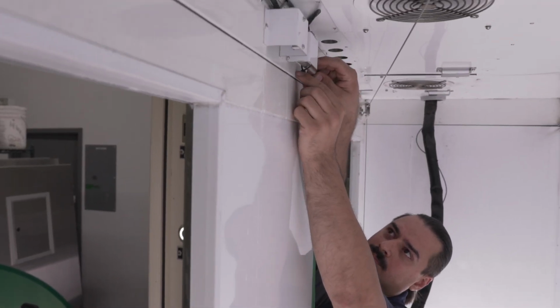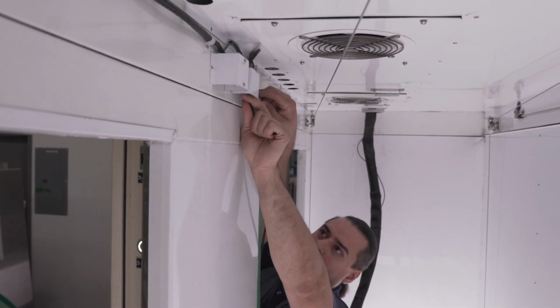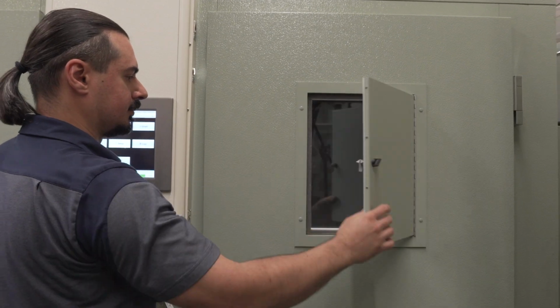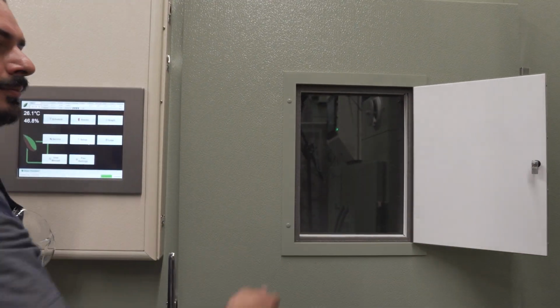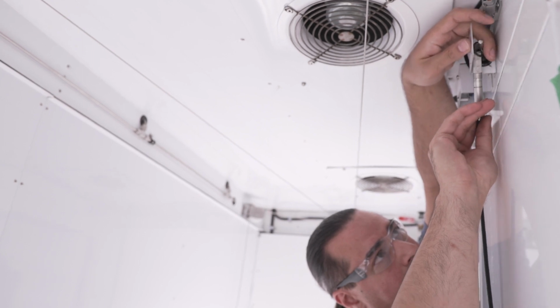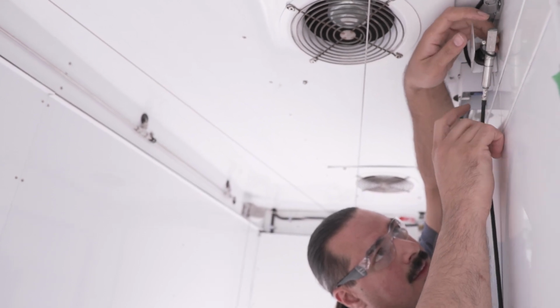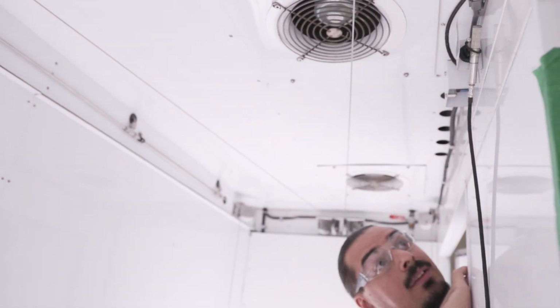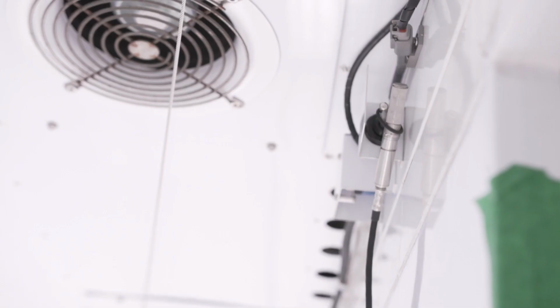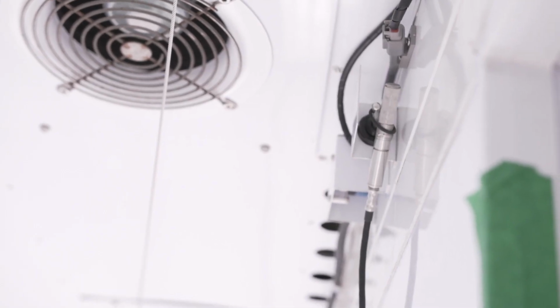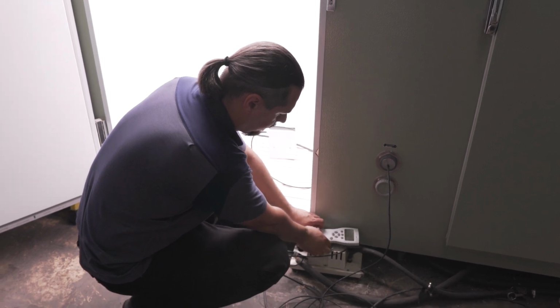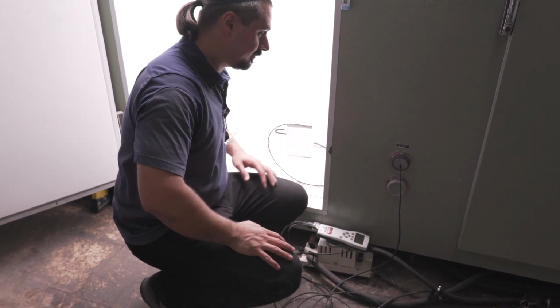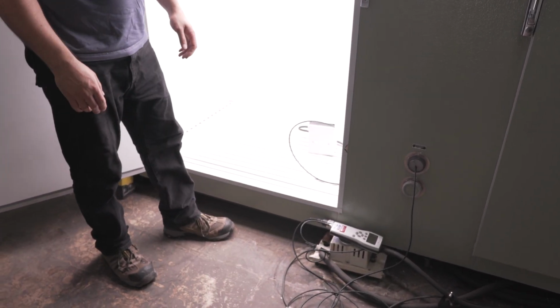Repeat the calibration check for the safety temperature sensor with lights off at max temperature and ensure it is receiving proper airflow. Note that when the lights are on, the safety temperature sensor will read 3 to 10 degrees higher than the chamber temperature and limit sensors, as its location is downstream of the lights, which give off heat. Older fluorescent and HID lighting will give off more heat, whereas LEDs give off less heat.